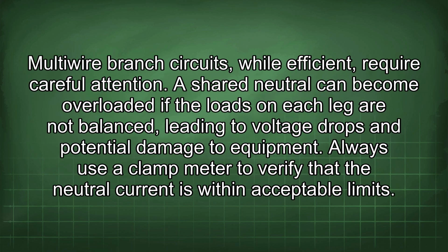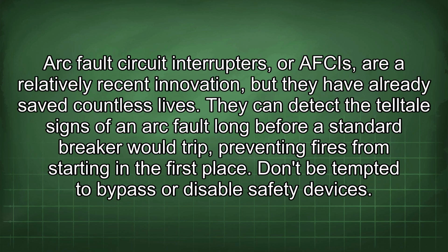Multiwire branch circuits, while efficient, require careful attention. A shared neutral can become overloaded if the loads on each leg are not balanced, leading to voltage drops and potential damage to equipment. Always use a clamp meter to verify that the neutral current is within acceptable limits. Arc fault circuit interrupters, AFCIs, are a relatively recent innovation, but they have already saved countless lives. They can detect the telltale signs of an arc fault long before a standard breaker would trip, preventing fires from starting in the first place.